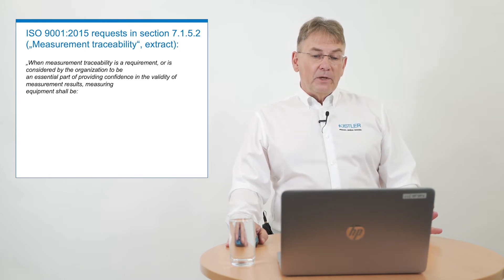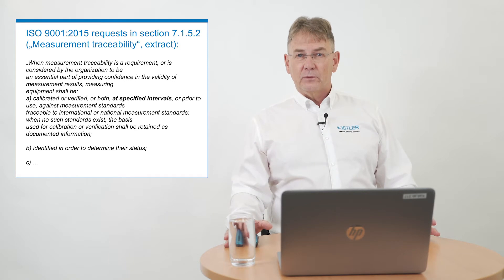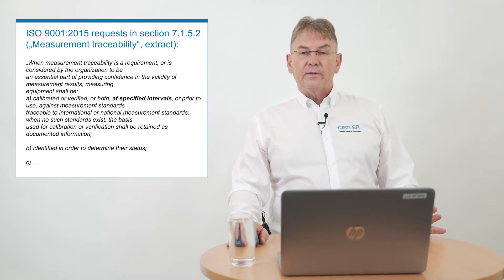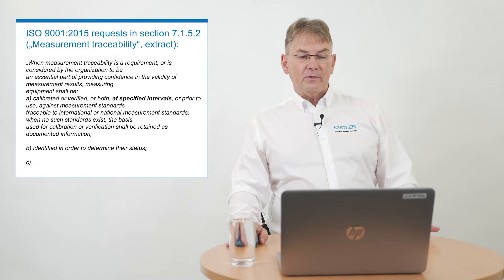The first thing we always do is take a look at norms. For most of you, ISO 9001:2015 is the mother of all norms, and this norm requests in section 7.1.5.2: when measurement traceability is a requirement or is considered by the organization to be an essential part of providing confidence in the validity of measurement results — which means nothing more than good quality of your product — measuring equipment shall be calibrated or verified or both at specified intervals, against measurement standards traceable to international standards. So we know calibration is mandatory and intervals have to be given, but it doesn't really help for everyday use.